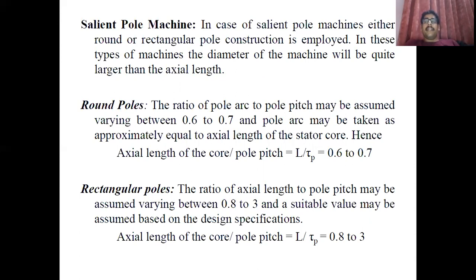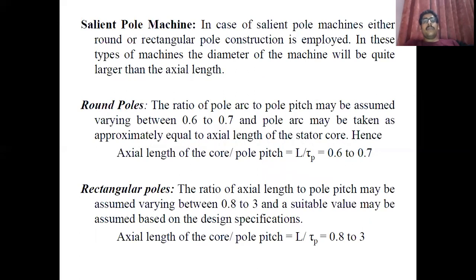The separation of D and L is done by two ways: number one, the ratio of axial length of the core to the pole pitch; and number two, peripheral speed. It depends upon the machine type. For example, in a salient pole machine — whether a rectangular pole or a round pole is used — the diameter of the machine is very large compared to its length. In that case you use L/τ to separate the diameter and core length.